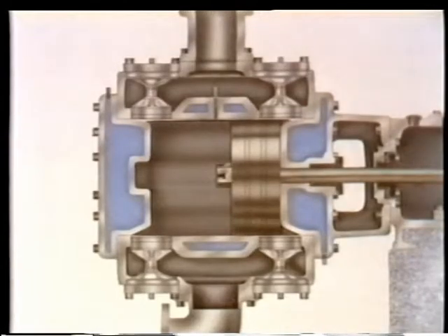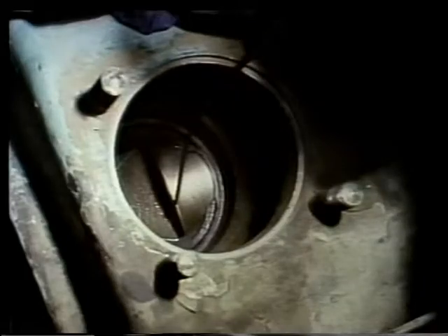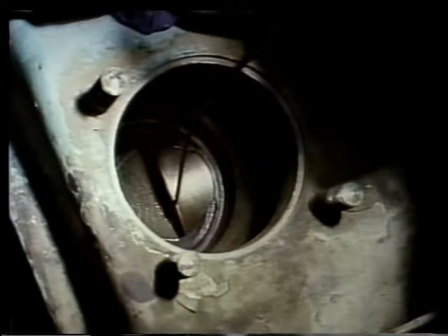To take these measurements, you need to remove one valve from the top end of the cylinder and one valve from the bottom end. Then insert a piece of soft solder larger than the specified clearance through the valve port to a point between the piston and the head. This procedure is the same for measuring both the top and bottom clearances.